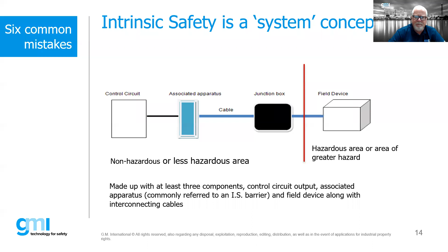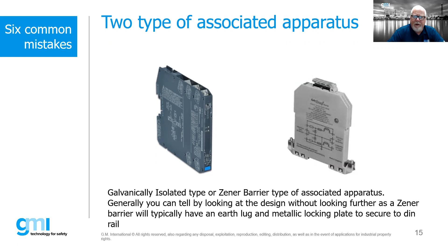There are two types of associated apparatus you'll typically find—multiple brands, but two major types: galvanically isolated type, and Zener barrier type. They're both known as associated apparatus. An easy way to tell the difference: if you look at the barrier on the right, it has earth lugs or earth tabs, which is generally a dead giveaway that it's a Zener barrier. The one on the left is a GMI, a galvanically isolated barrier. They do the same thing but operate differently, and each has advantages and disadvantages we'll discuss.